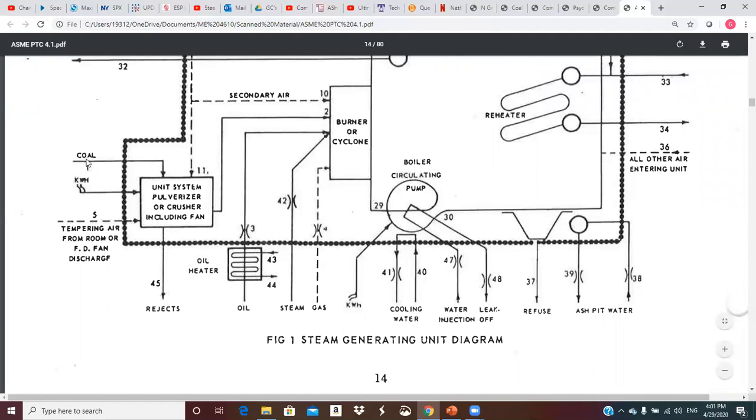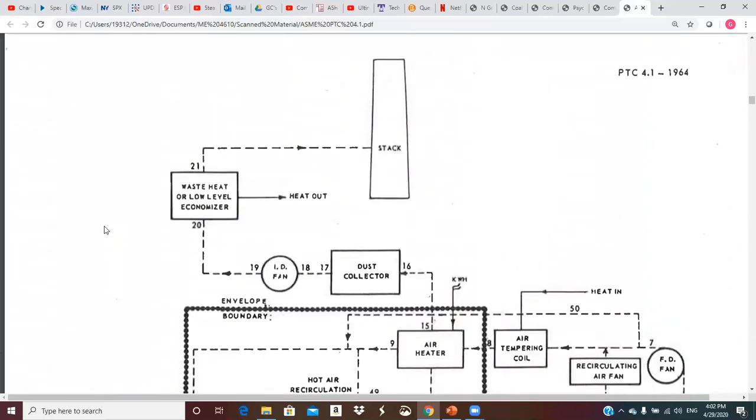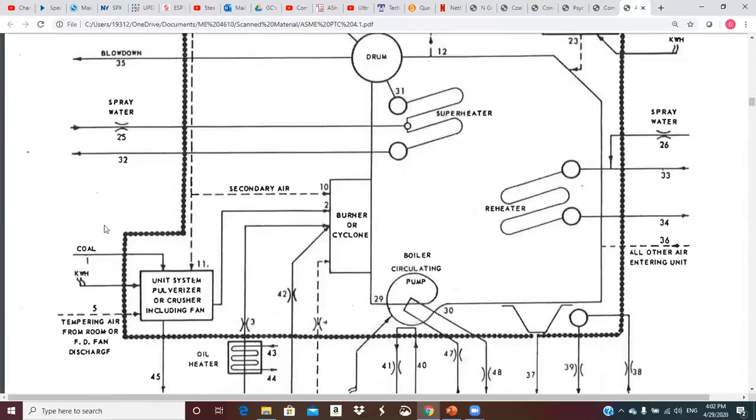So let's come down here. And good old number one is coal. So coal crosses the boundary into the analysis, and it goes into unit system pulverizer or crusher, including fan. So that's inside the control volume. We have some electrical energy potentially going into this. This could be motor driven pulverizers, et cetera. It could be fans in here, including fan. So it takes electrical energy to run those motors. That crosses the control volume. That has to be quantified.